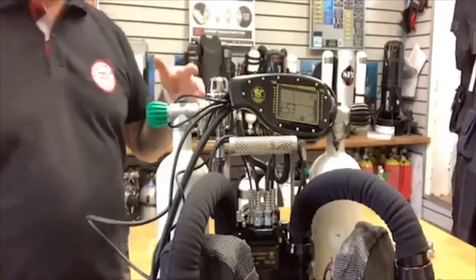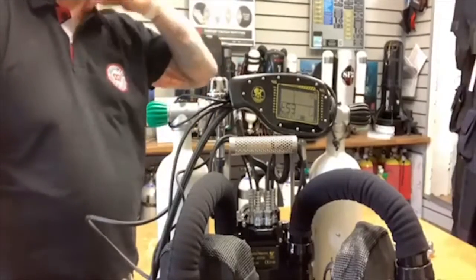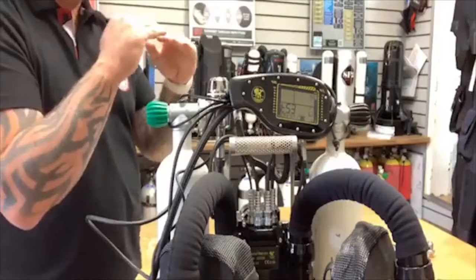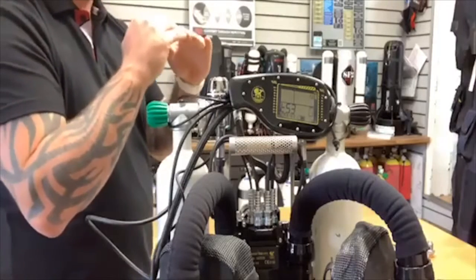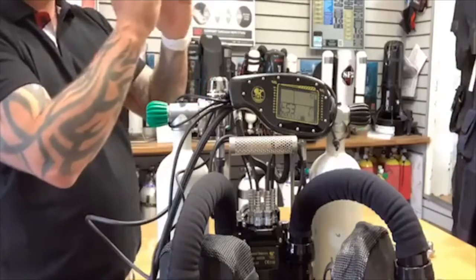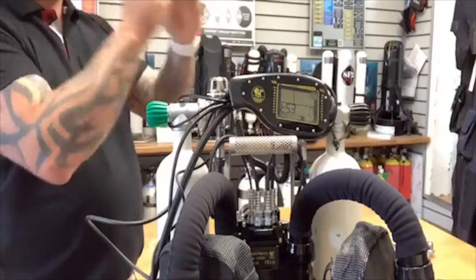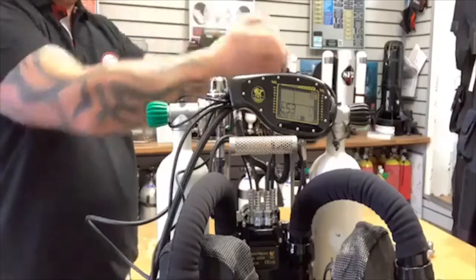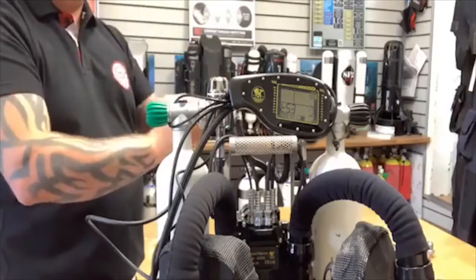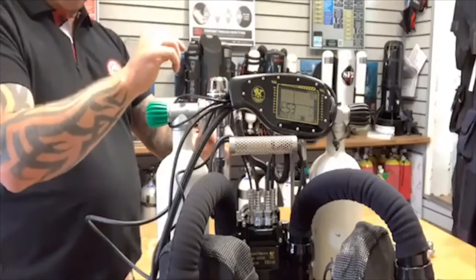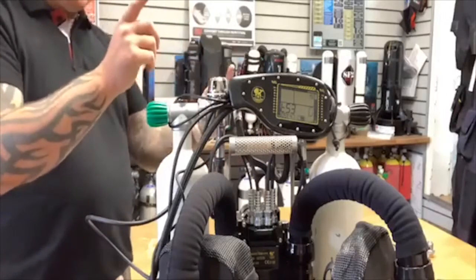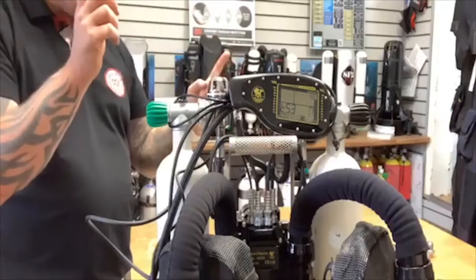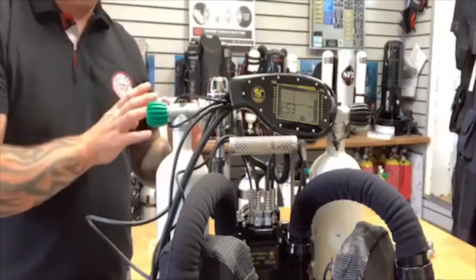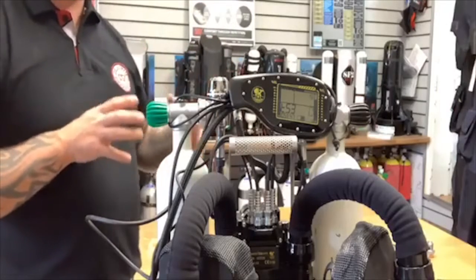It injects oxygen and takes it all the way up to the highest limit. So it waits for those cells to settle with pure oxygen blowing onto them. Once it's got the highest limit, it says, okay, great, that's what oxygen should be. Based on oxygen, I'm now going to inject diluent at a lower limit, and I'm going to check that that is 21. So if that was oxygen and that was 21, are they the difference that I expect to see as well? And so that way it can confirm whether the gas you put inside, the calibration was correct.